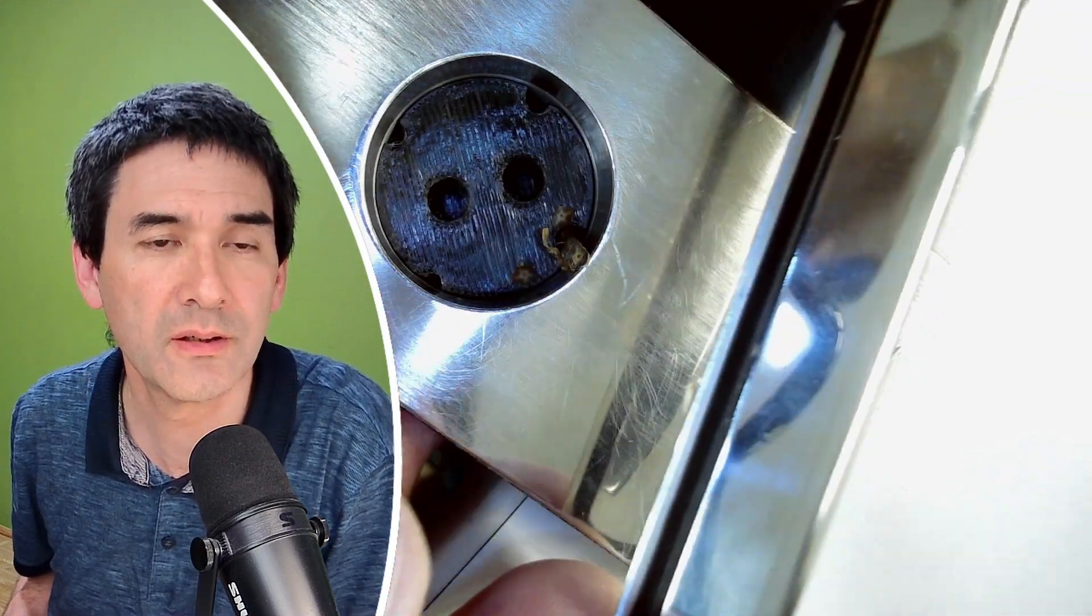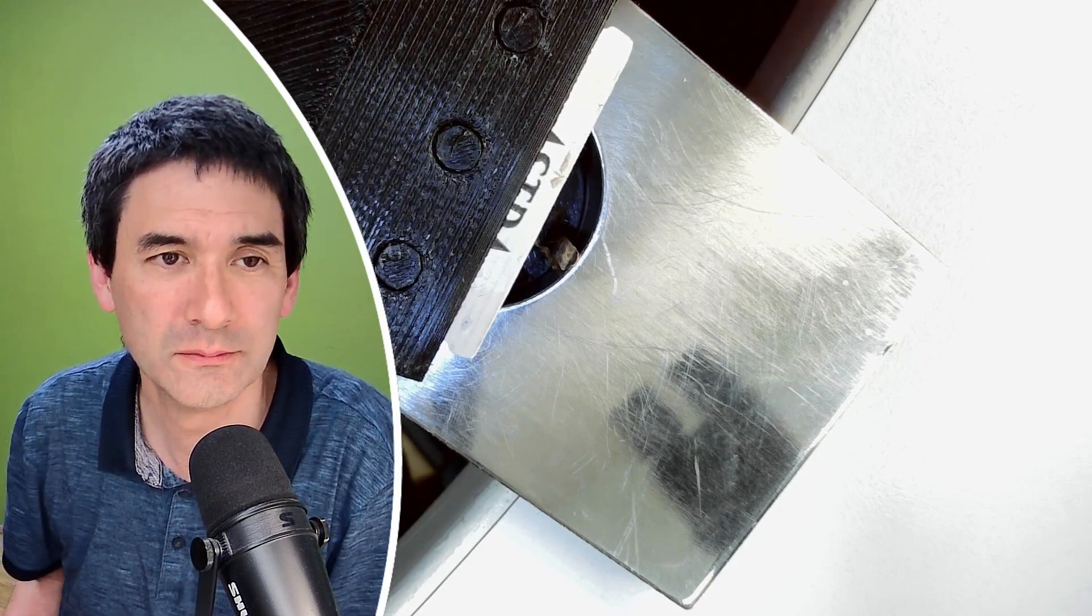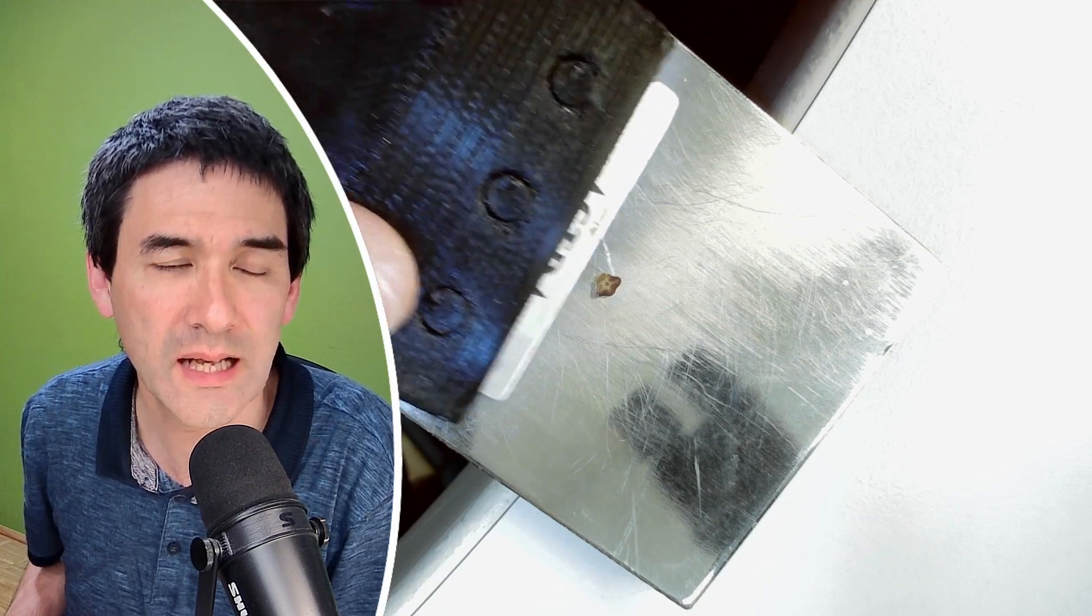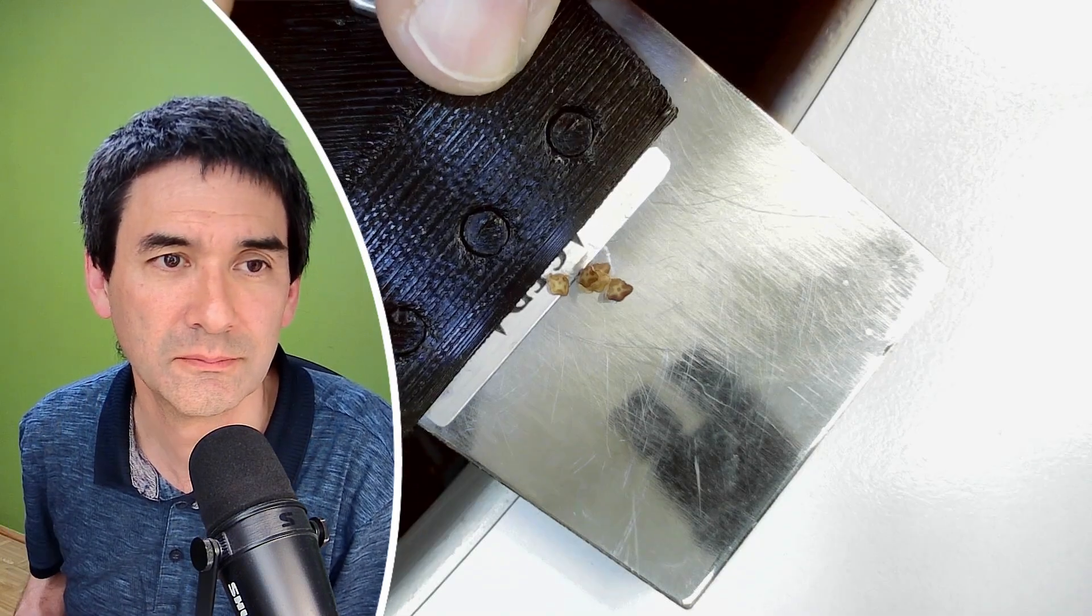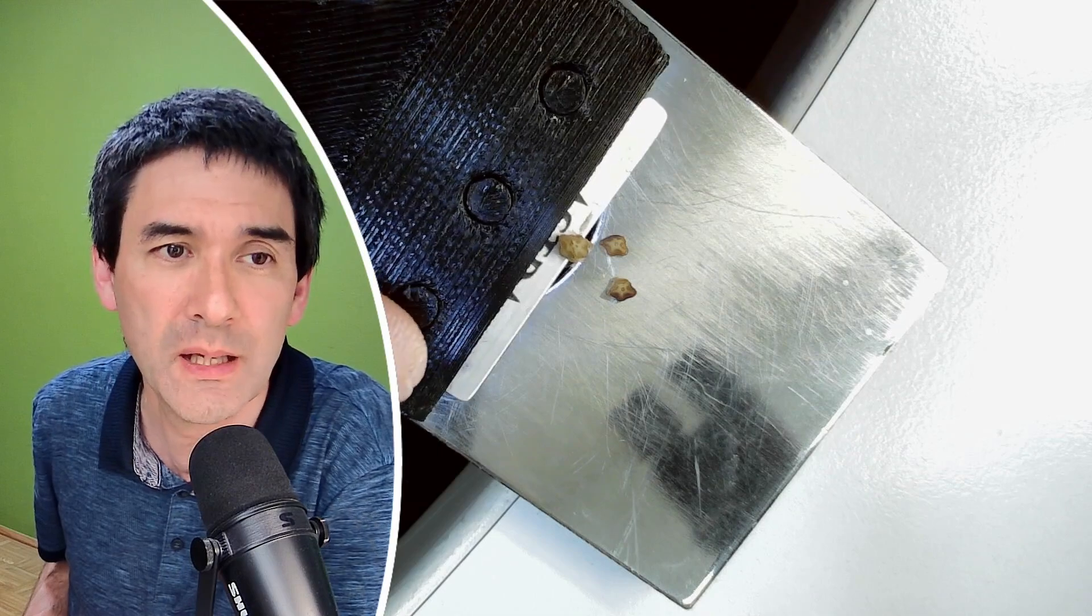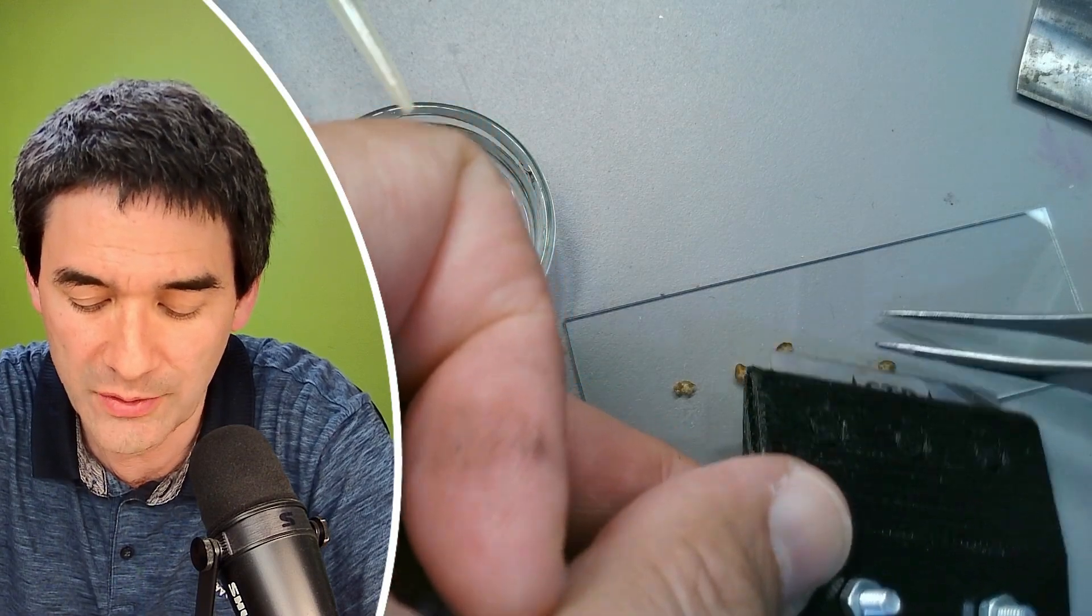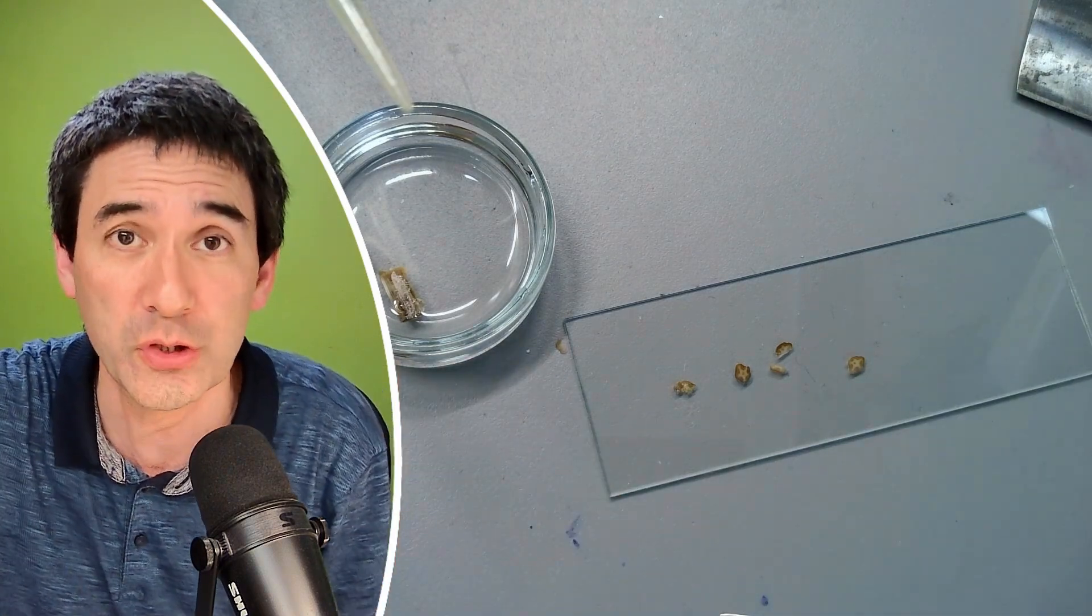Last but not least let's try this one here. This one actually has the advantage that I'm able to put it directly very flat on the microtome. I'm still sliding over it so it did not advance enough. This one cuts very smoothly and very lightly, this was a very thin one. I think I like this one as expected the most. First of all I have a lot of stability because the angle of the blade is always the same, it's a sharp blade, and because it's disposable I don't have to sharpen it. Let's put this under the microscope. I'm not going to use a cover glass, I'm just going to have a first look.